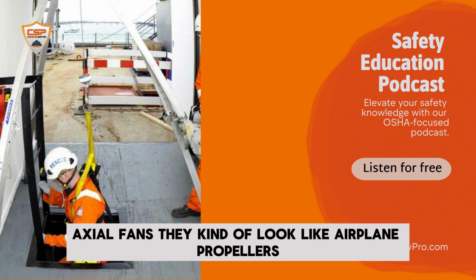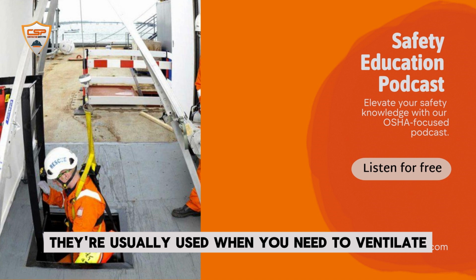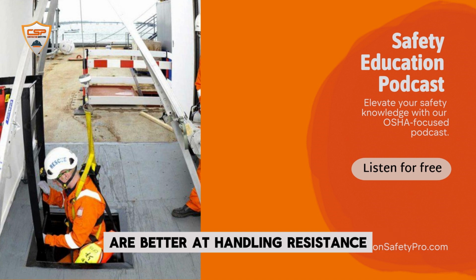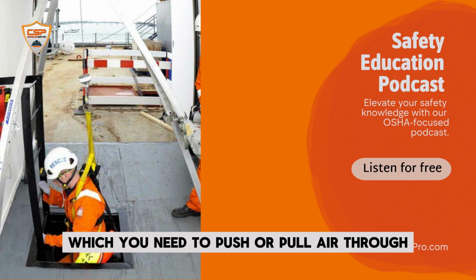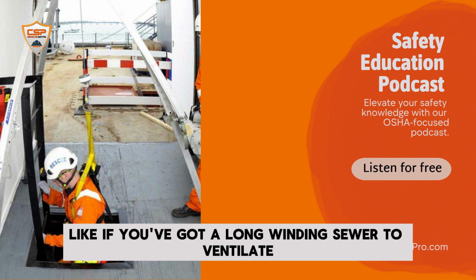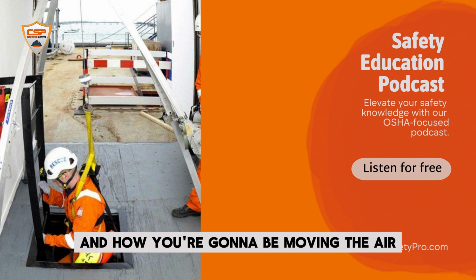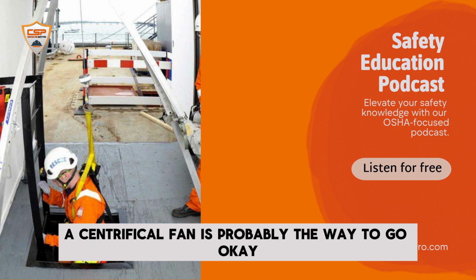Axial fans kind of look like airplane propellers. They're great for moving a lot of air quickly when there's not much resistance. They're usually used when you need to ventilate a space that's not very deep and doesn't have a lot of ductwork. Centrifugal fans, sometimes called squirrel cage blowers, are better at handling resistance, like from long ductwork. They can generate more pressure, which you need to push or pull air through longer distances or more complicated systems. Like if you've got a long, winding sewer to ventilate, a centrifugal fan is probably going to be your best bet because it can overcome that resistance. So really, it comes down to the layout of the space and how you're going to be moving the air. That makes sense. If you need long ducts to reach a certain part of the space, a centrifugal fan is probably the way to go.